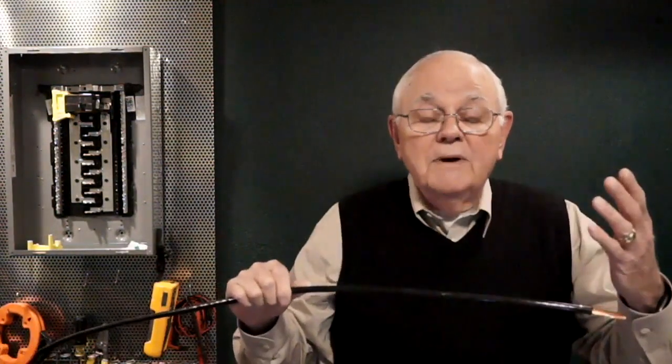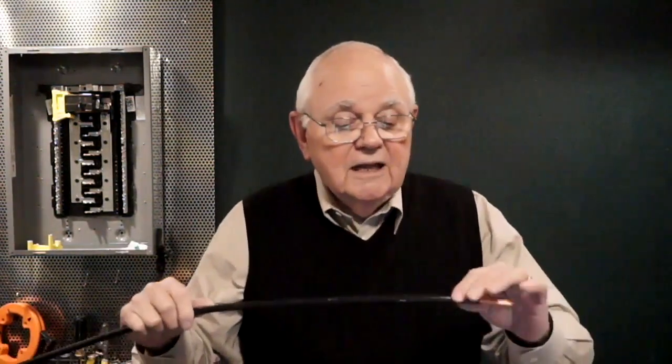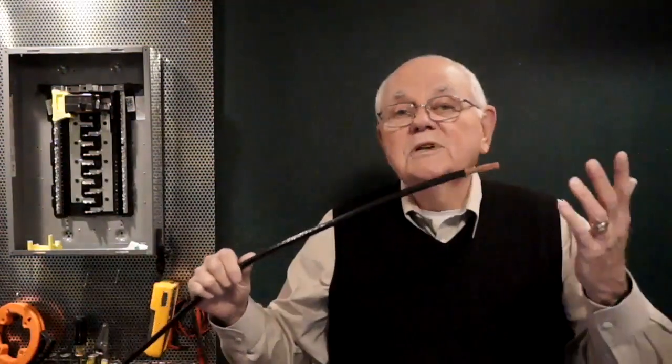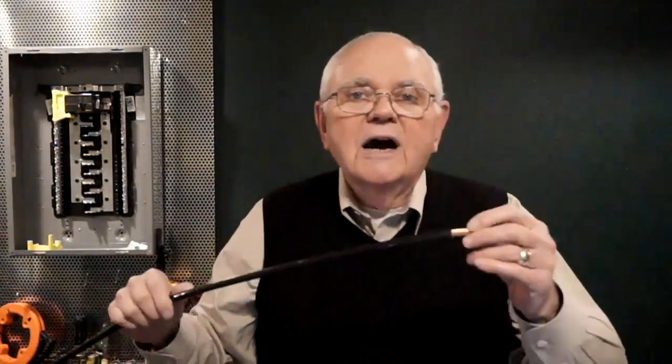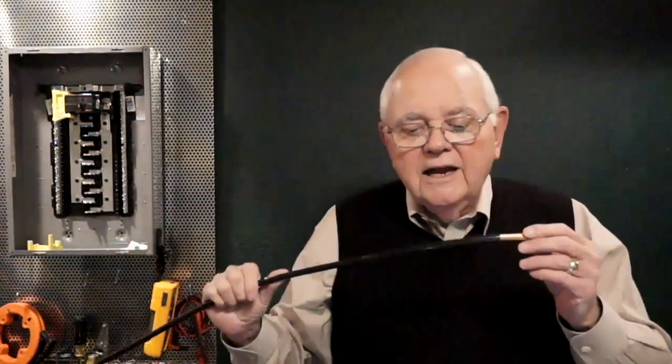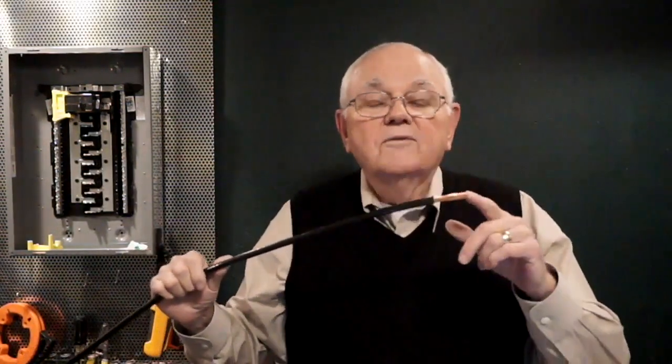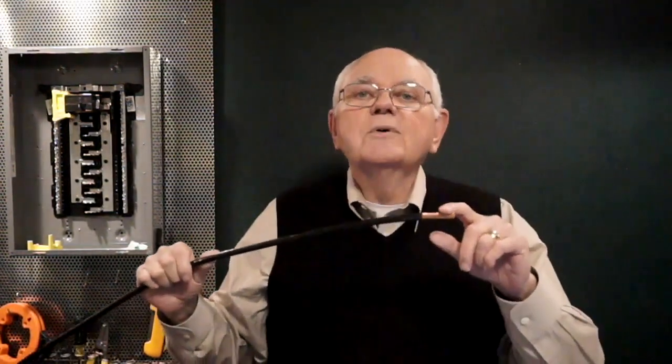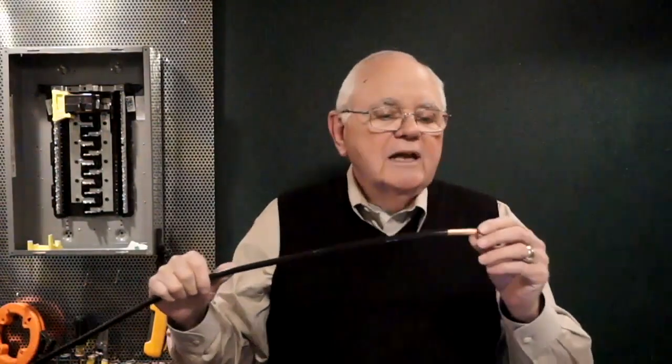So let's talk a little bit about this more in detail. Copper is probably our most common conductor, right? We also have our AA8000 series aluminum wire that we use, which is very good. But copper is probably our primary type of conductor that we use to carry electricity out in our premises wiring system. Now, there are three different types of conductor material identified in the code: copper, the aluminum I mentioned, and copper-clad aluminum, where they extrude a thin layer of copper over the aluminum when they manufacture it.